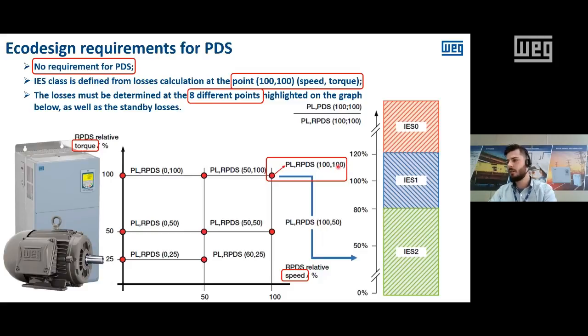speed and 100% torque. Again, in the regulation, they defined loss values for a power drive system, and these values were defined as IES1. To be IES2, you have to have a power drive system with 20% lower losses than the IES1. Therefore, you are going to be IES2.